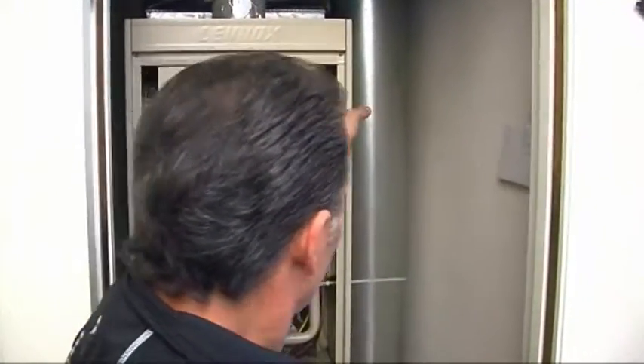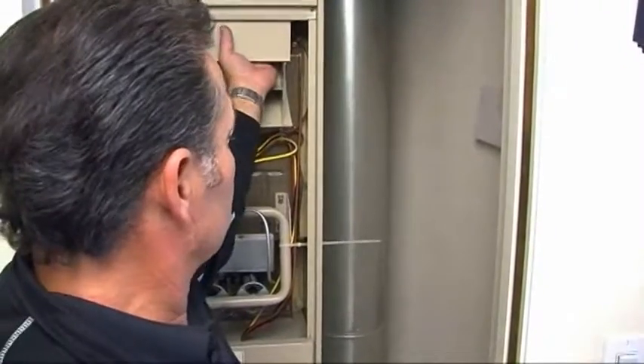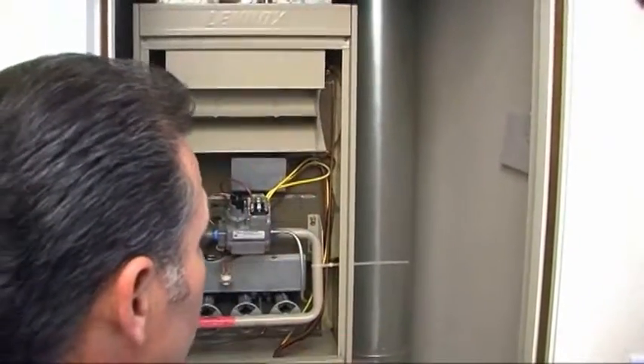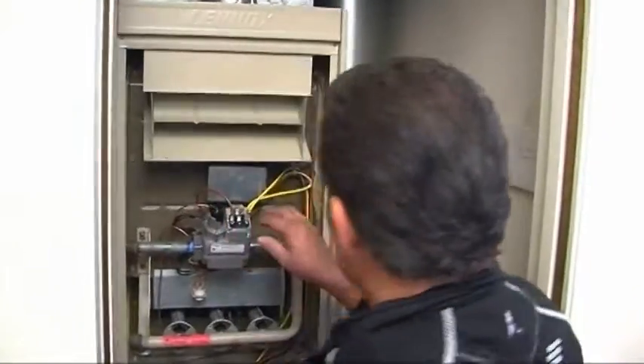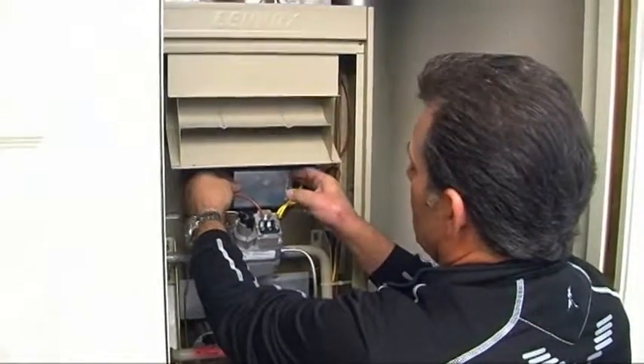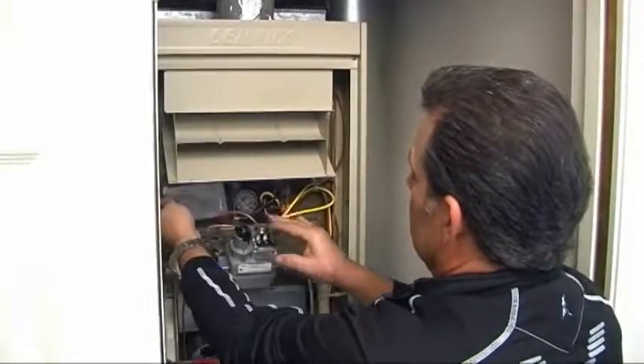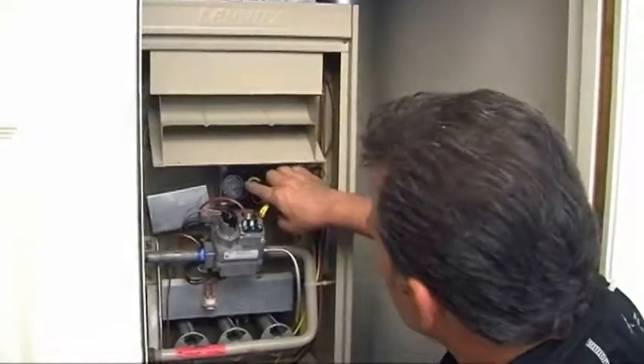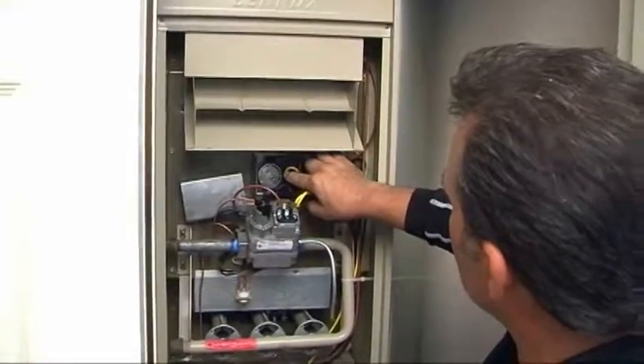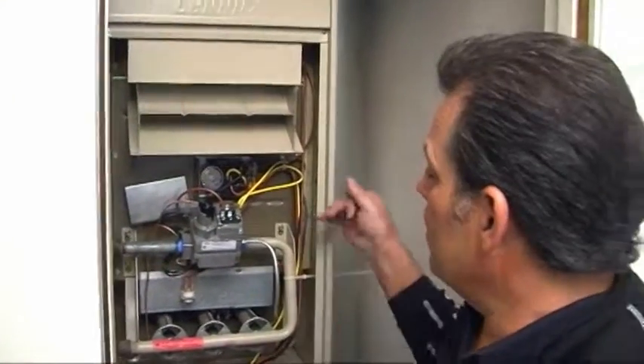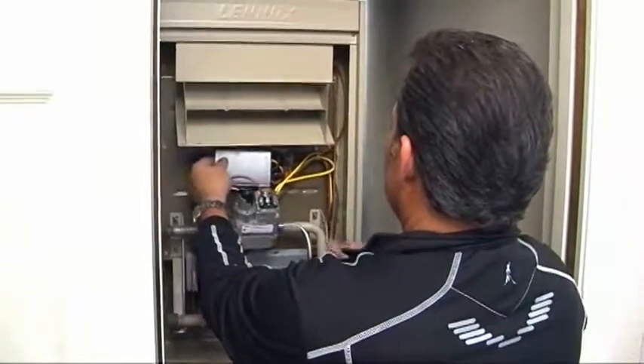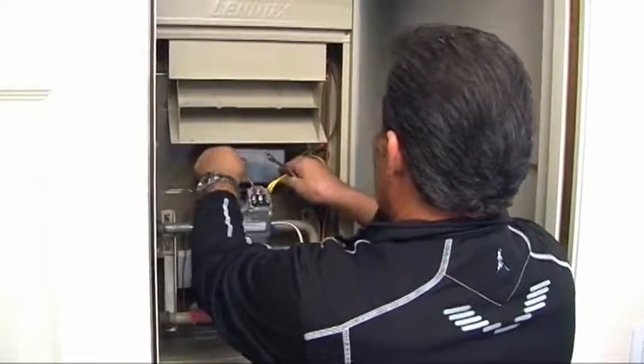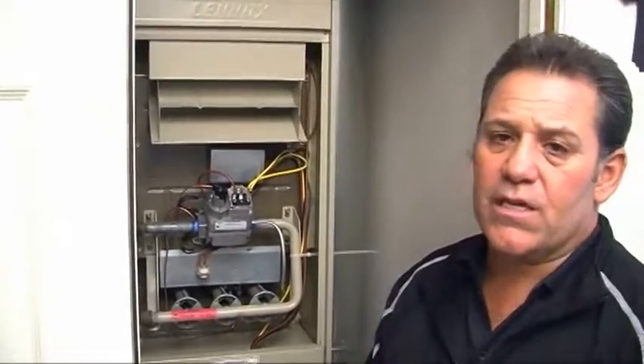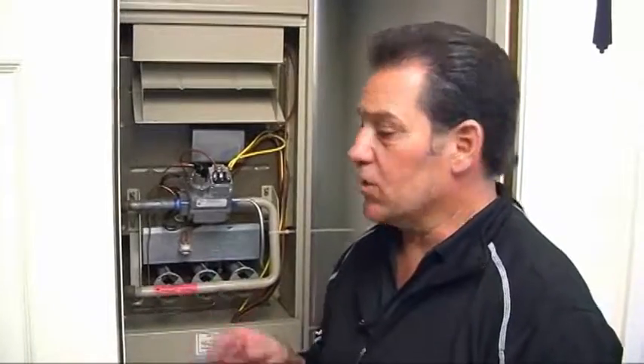Okay, let me show you some of the safeties in this furnace before we leave. Right here on the side, which actually makes contact in here, is my vent safety. Then out of the vent safety comes to what I would call the heat exchanger thermostat. This has two settings on it, 200 and 160. That means that when the heat exchanger reaches 200, the fan motor kicks on, and when the thermostat has met temperature, the fan continues to run, and when it comes down to 160, it shuts off.